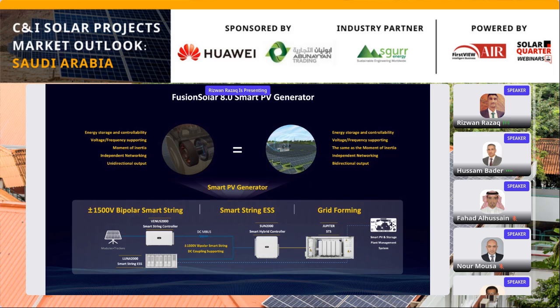As you can see in the overview, we're utilizing a plus minus 1,500 volt bipolar smart string architecture. This is a DC coupled energy storage system, where we will be utilizing the smart string controller in the field and the smart hybrid controller, which will be localized to where the transformer station would be located. We're also providing the Jupiter STS station, a larger capacity transformer station.